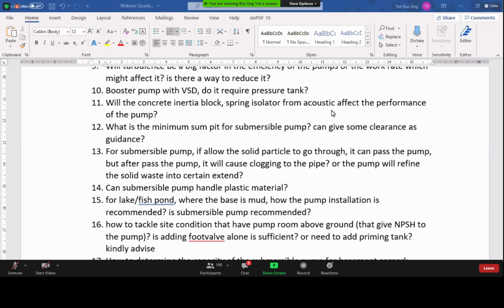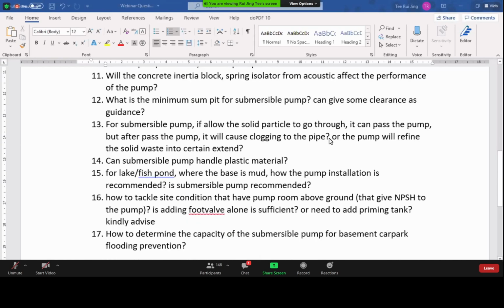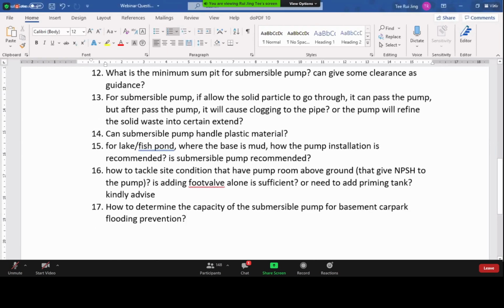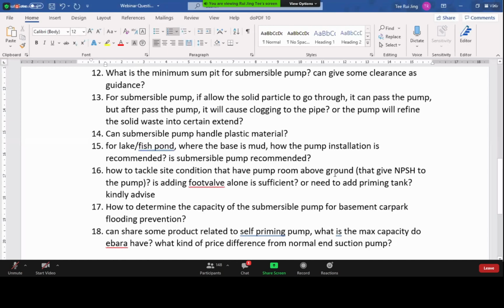Number 12, what is the minimum sump pit for a submersible pump? Okay, I just got this question just now, so I don't know whether this is the same engineer that asked me this. Now, for submersible pumps, because of the way it operates, your pit sizing is very important. And the reason is because unlike a normal cold water pump where you have a motor on top and the motor is cooled by the fan on that motor, yeah. So when you call it a TEFC motor, it basically means totally enclosed fan cooled motor.